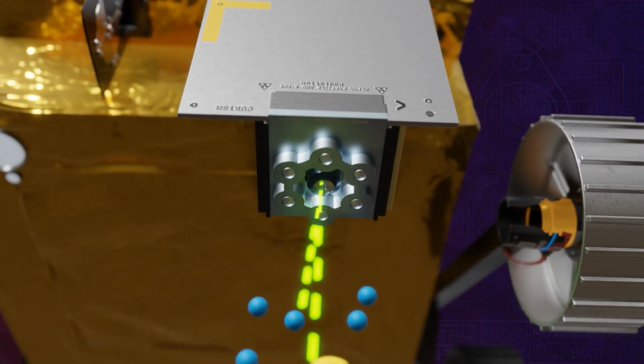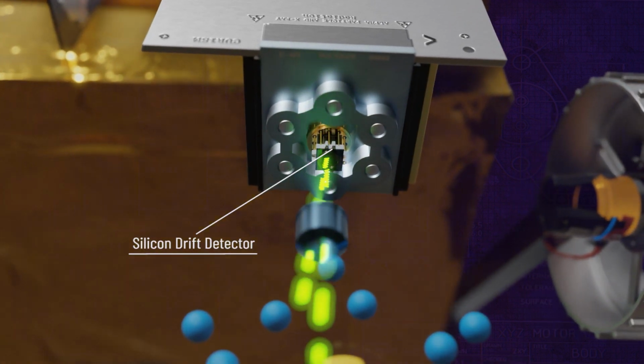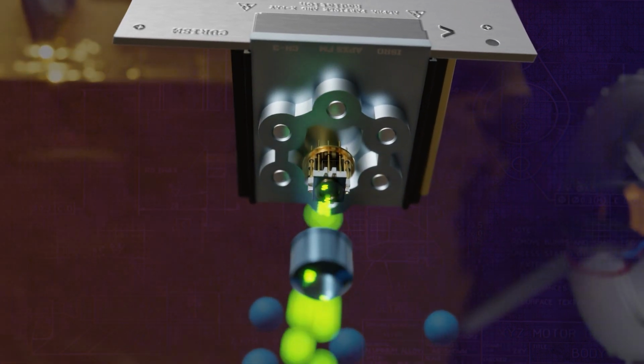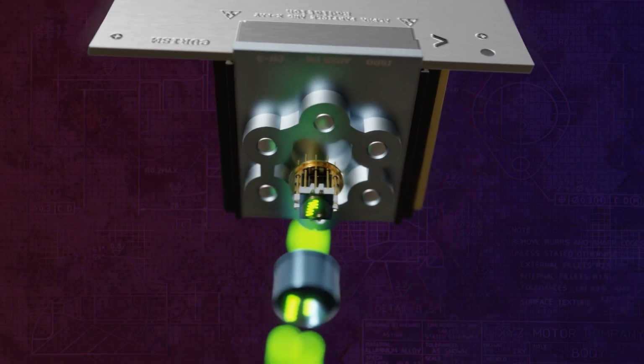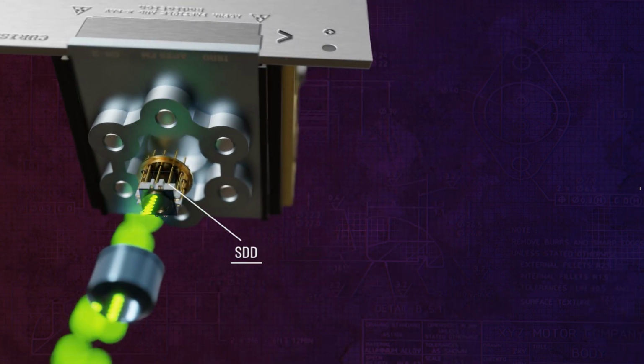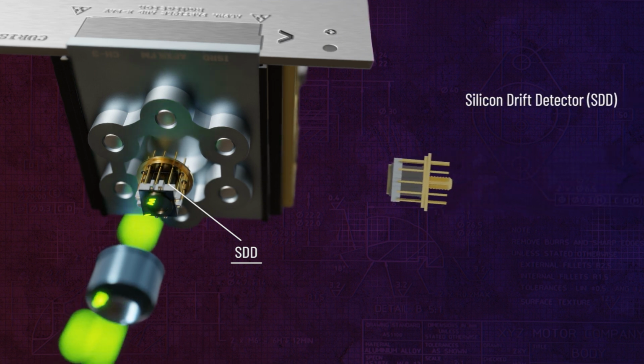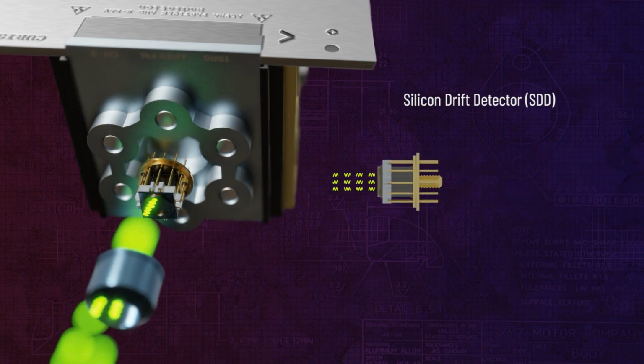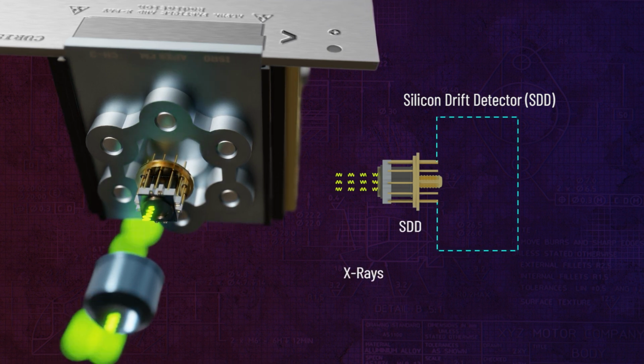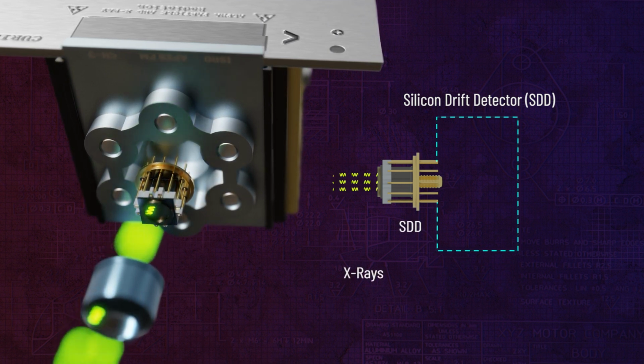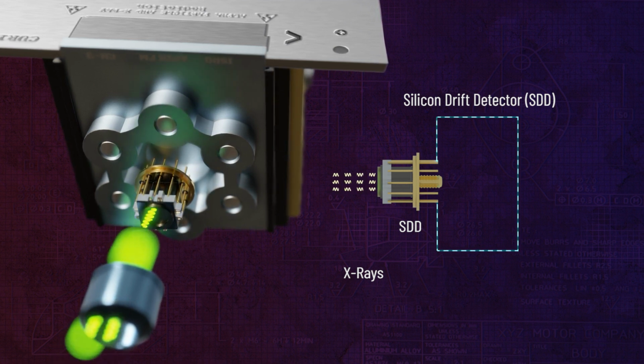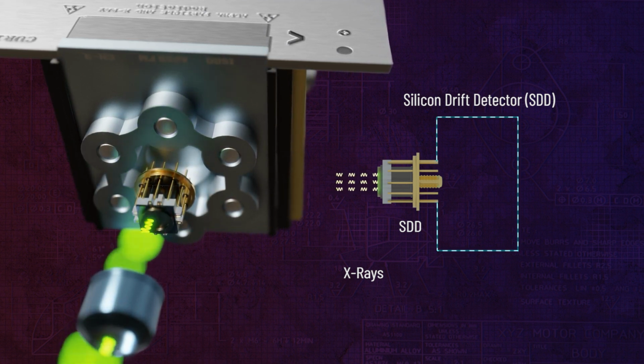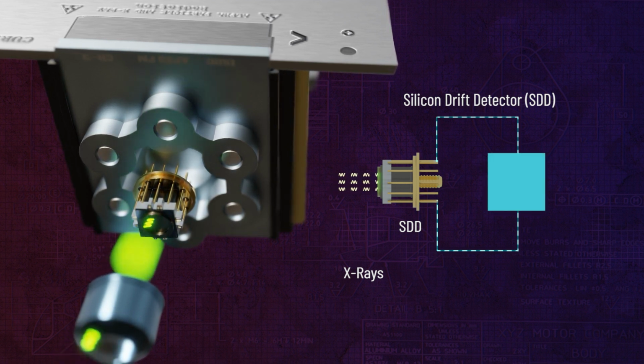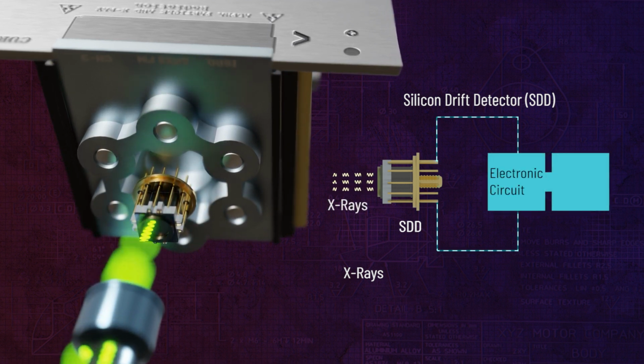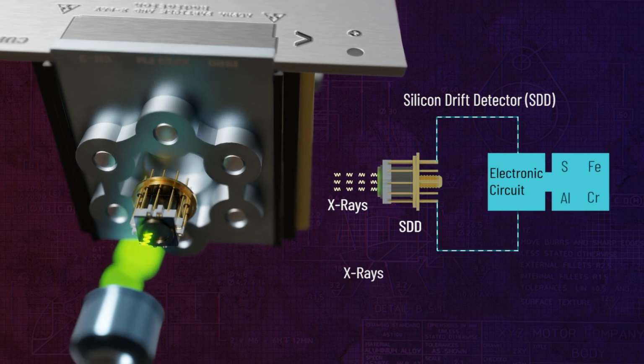A detector, known as an SDD or silicon drift detector, is there at the center of the emission ring, to capture these characteristic X-rays emitted by each element. The silicon drift detector, made from semiconductor material silicon, effectively detects X-rays, since interactions between X-rays and silicon generate electric signals. The alteration in the electric signal is directly proportional to the energy of the incoming X-rays. With the help of suitable electronic circuitry, these signals can be processed, and the elements are detected.